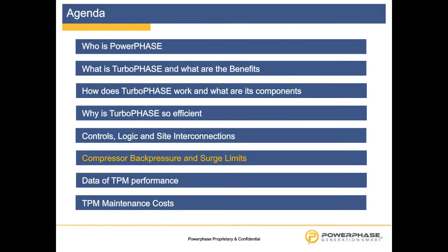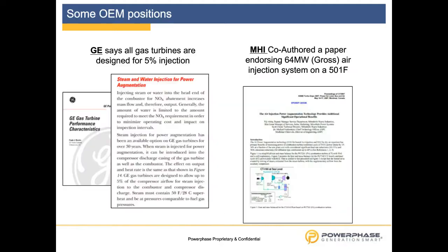So the next point on the agenda is questions that we normally receive on compressor back pressure or surge limits, and I would like to address this as follows. There are some OEM positions. OEMs state in general that, for example, a 5% injection into the compressor discharge is allowed, that the gas turbines are designed for it. Other OEMs endorse the dry air injection technology, especially for a particular frame in a particular area. These OEM positions are available and published.